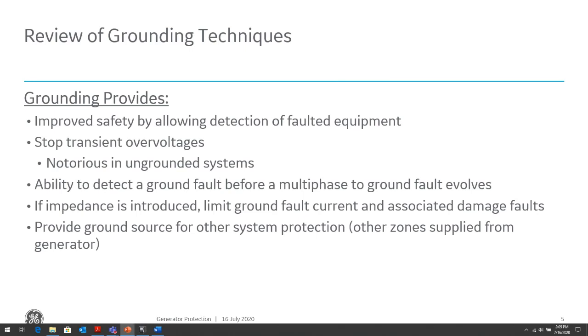For ungrounded systems, if we recall, when we have a fault in an ungrounded system, the neutral shifts. When the neutral shifts, the faulted phase shifts to the neutral point, and then the ungrounded phases shift to the phase-to-phase voltages. So we have very high transient overvoltages that can damage the equipment and break down insulation.